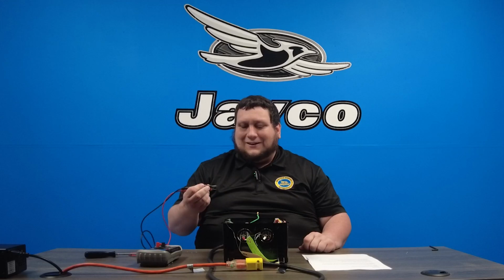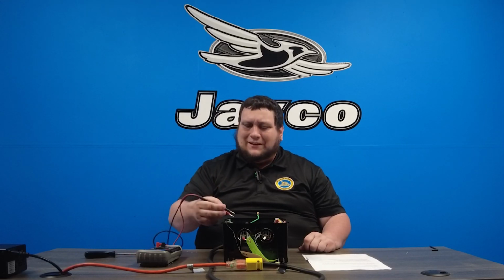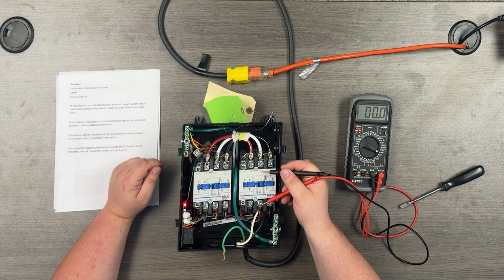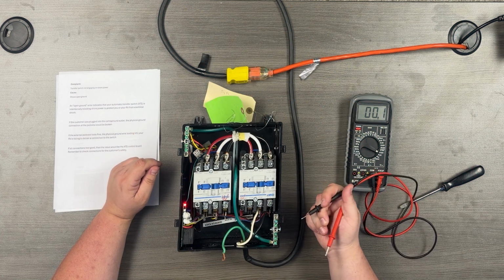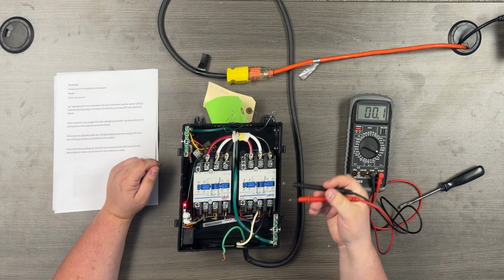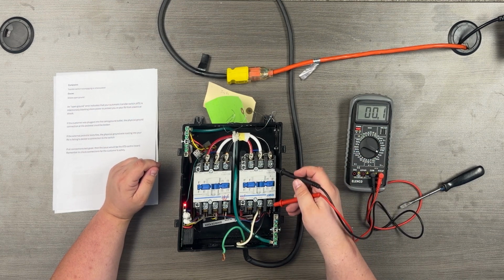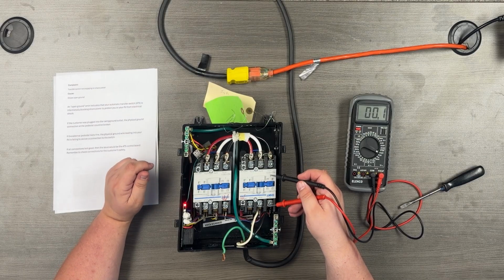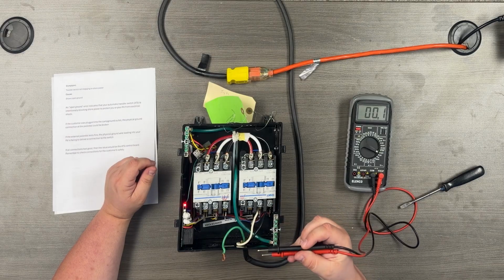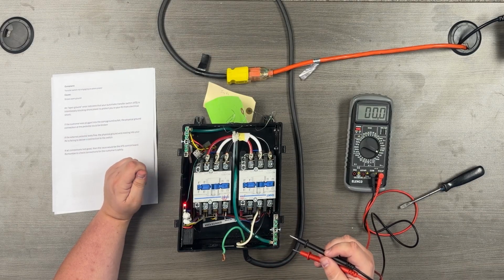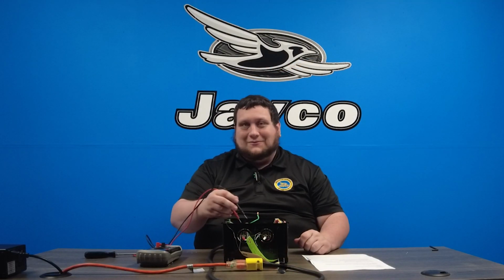What I want to really emphasize is that we've had a couple of reports written in where people are saying, oh, I'm not passing voltage unless I am pushing down the contactor here. Please don't do that. Because what you see right here, if we look a couple inches this way, a couple inches that way, I've got my hot lines. There's a reason I'm holding it and doing it with my meter leads here and not with my fingers, because I am hot right now. I don't want to accidentally, while I'm playing around in here with this live transfer switch, touch my hand across the hot and neutral line. Now I've been electrocuted. We don't want that to happen.